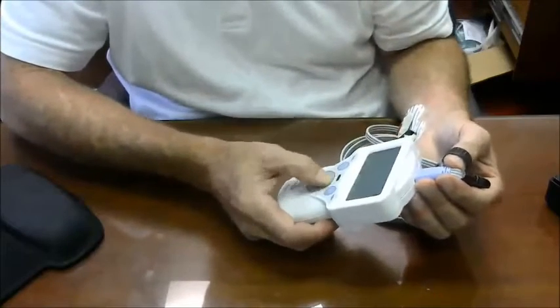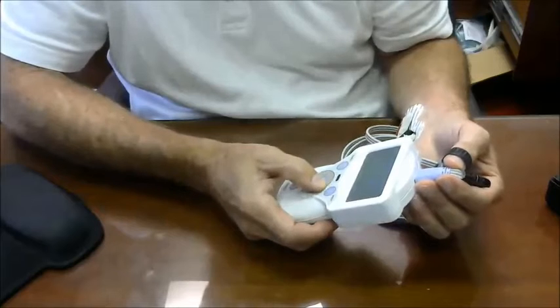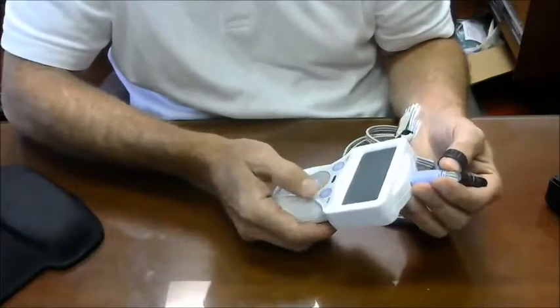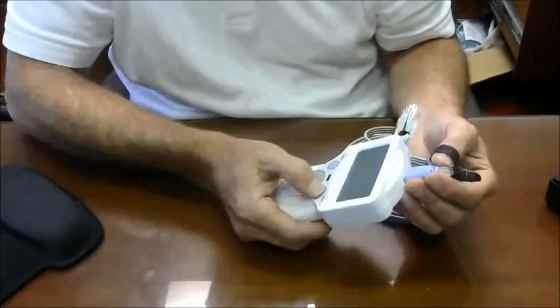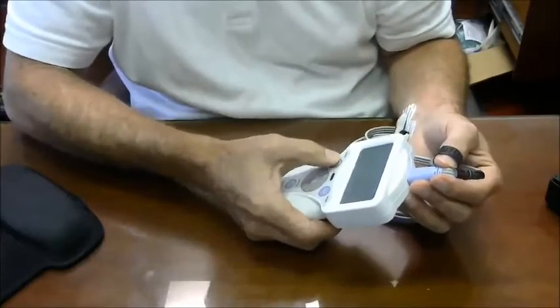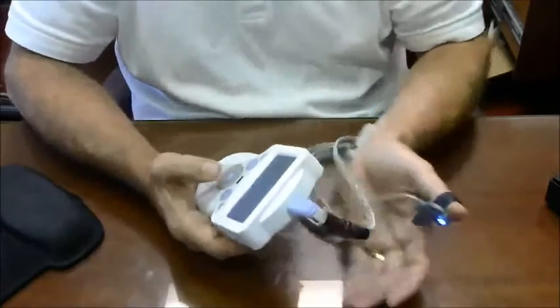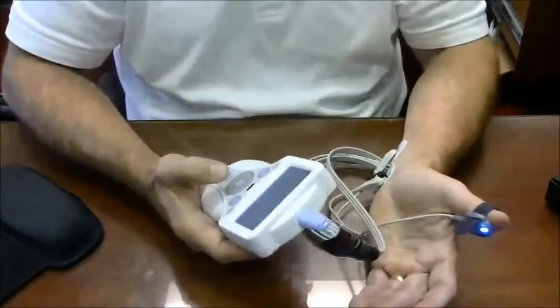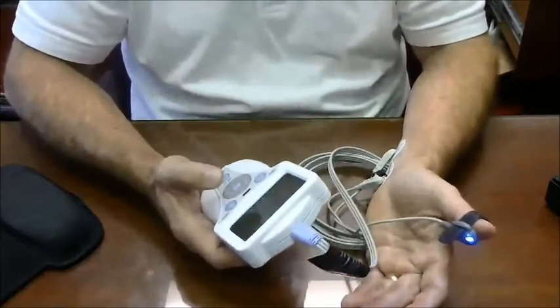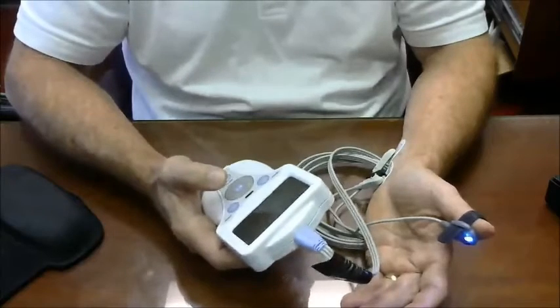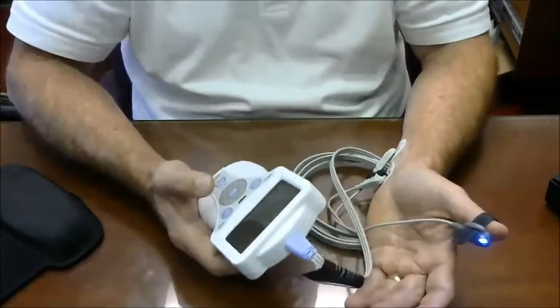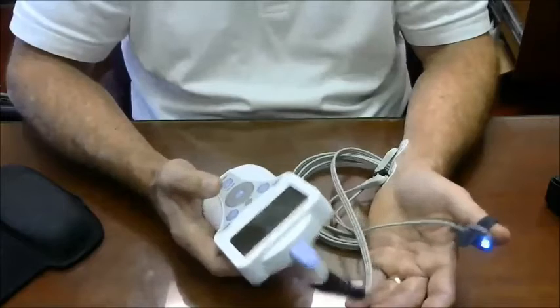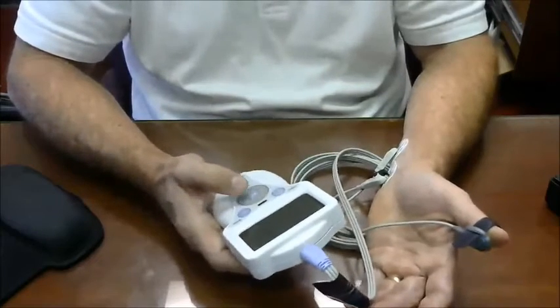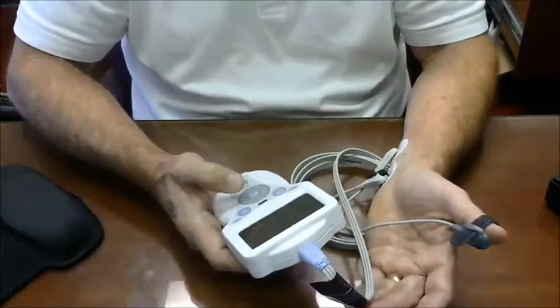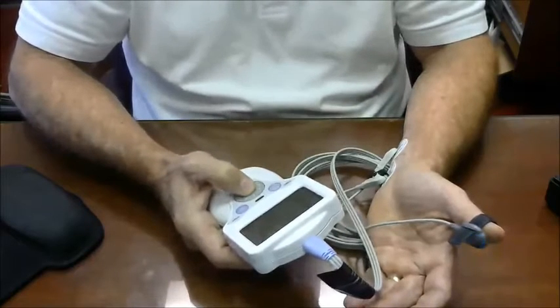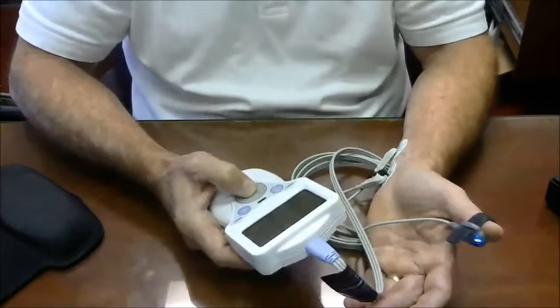In fact, let's do that. We're going to bring that down to 20 seconds. And I'll press enter. And I confirm and say yes. And then I press the menu key. So now what I'm going to do is I'm going to put it in automatic mode. Now typically you would do this, like I said, possibly in induction, because you give the rocuronium, and sometimes it takes 2 minutes for that paralytic to set up, and this is a way you can observe it going down. So the patient being paralyzed. So I'm going to press the stimulate button and hold it for a full 1.5 seconds, and that'll put it in automatic mode.